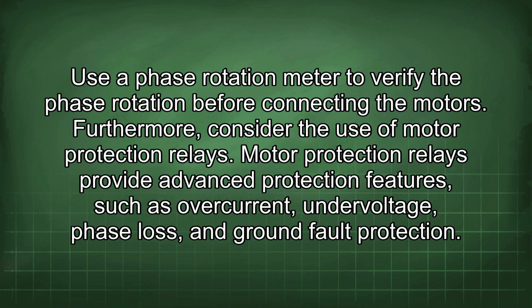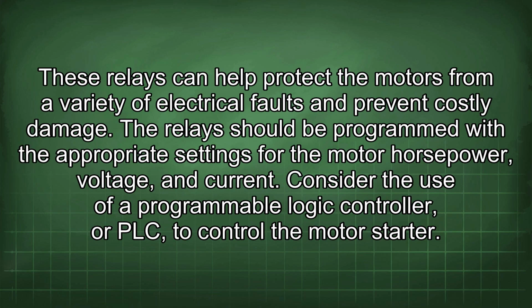Furthermore, consider the use of motor protection relays. Motor protection relays provide advanced protection features such as overcurrent, undervoltage, phase loss, and ground fault protection. These relays can help protect the motors from a variety of electrical faults and prevent costly damage. The relays should be programmed with the appropriate settings for the motor horsepower, voltage, and current.